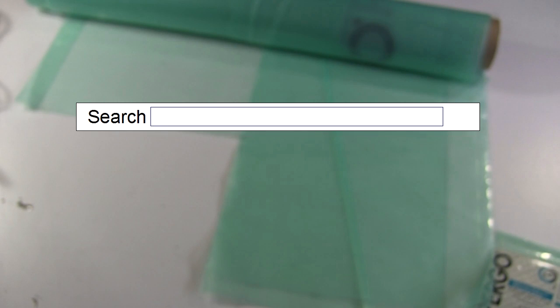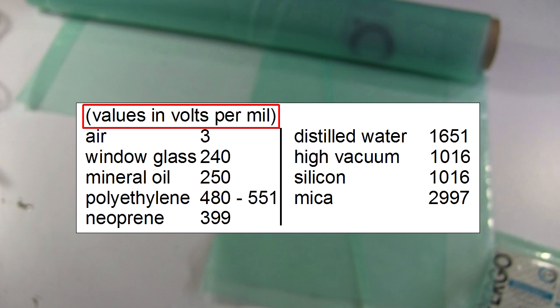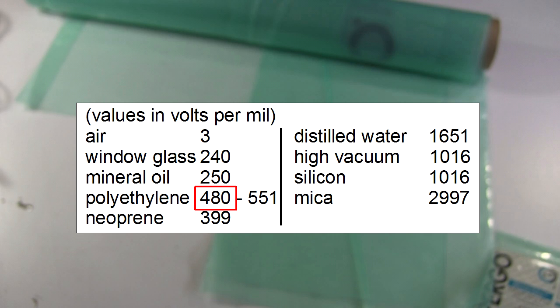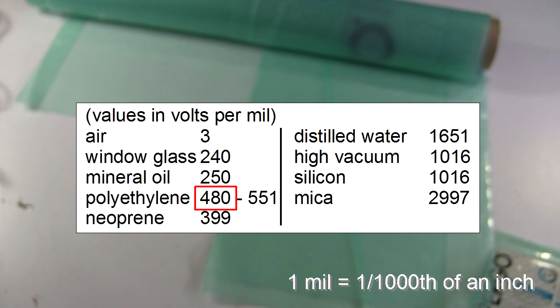The first thing you have to do is search online for the breakdown voltage, or dielectric strength, of the material you're planning on using. It'll give some value, like so many volts per thickness. Often you'll find a range. For example, 480 volts per mil to 551 volts per mil. Pick the lowest one to be safe. One mil is one thousandth of an inch.